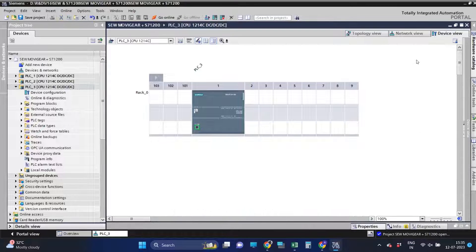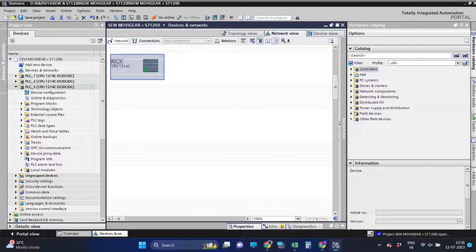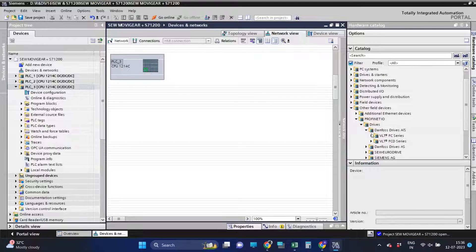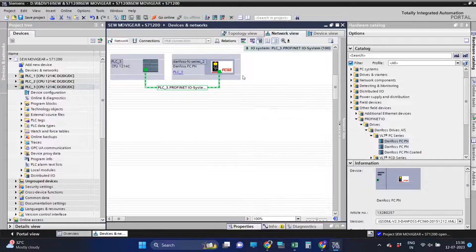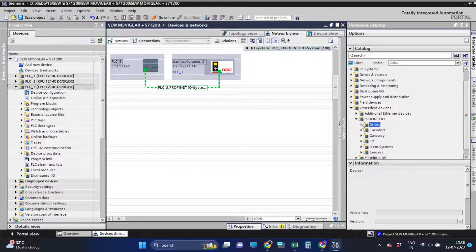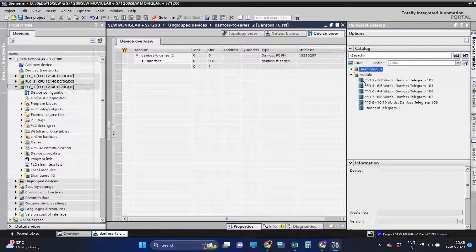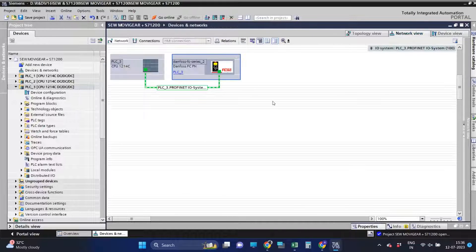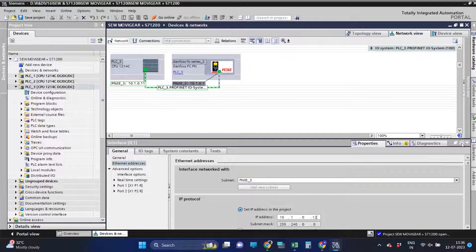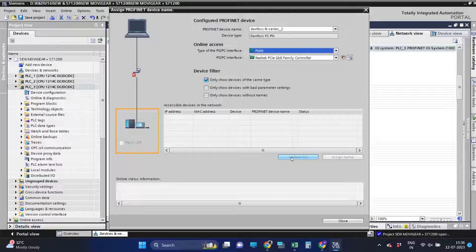After adding the CPU, let's add the Danfoss FC360 drive in the program. After adding the drive, let's choose the range of control and status word. Here we have chosen PPO3, that is two control words and two status words. We have also changed the IP address of the drive as well.